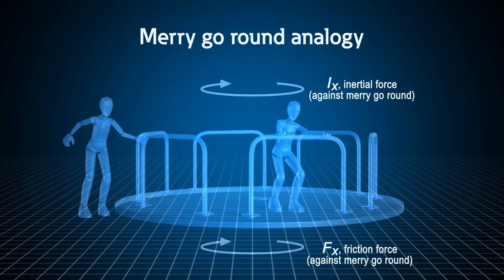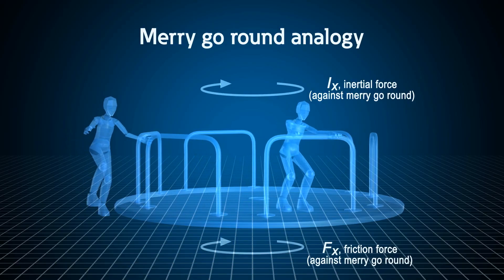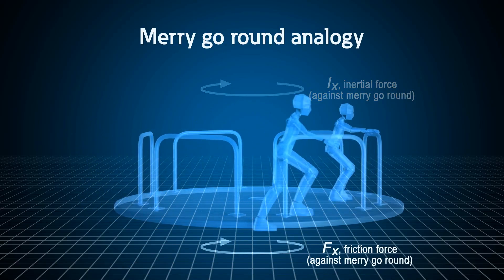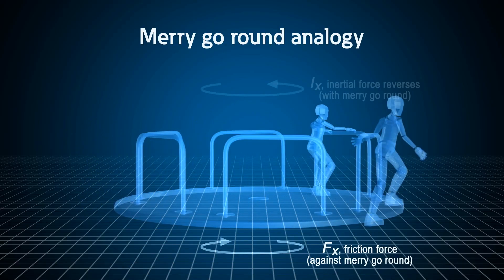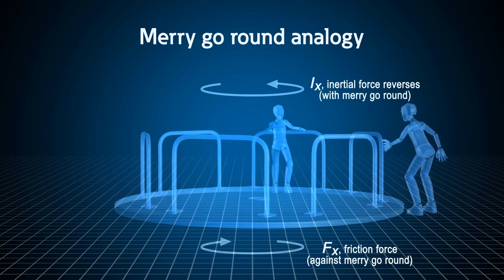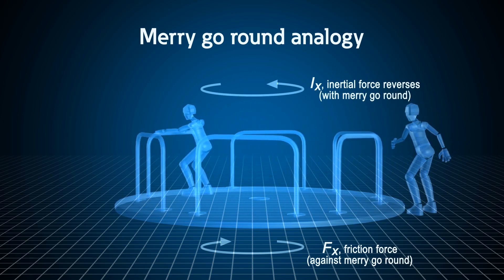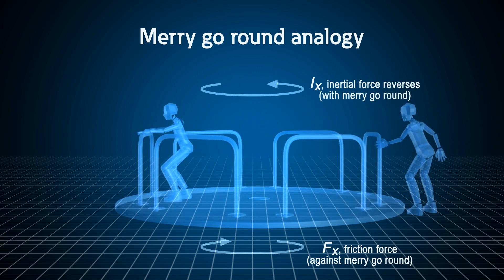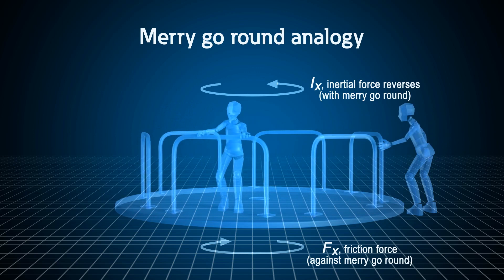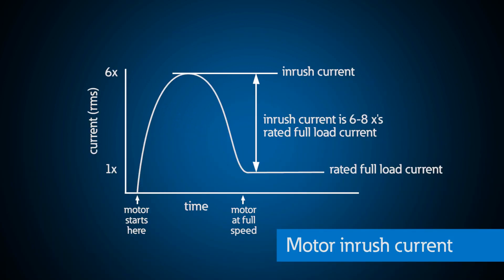This is like spinning someone on a merry-go-round — it's hard to get them spinning. You might even run around in a circle a few times while pulling on the bar. But once they're up to speed, it's easy to keep them moving by pushing on one of the bars as it goes by. A typical motor inrush current when started across the line, meaning directly connected to the 60 Hz power system, is six to eight times the rated full load current.